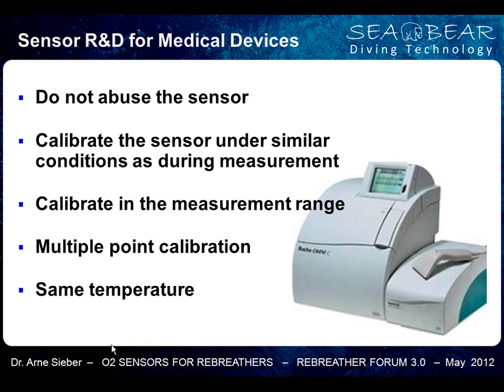The next point is, do a multiple point calibration. Define a span, and within this span I want to measure. I make a calibration point at the bottom, I make a calibration point at the top. This is the minimum I want to have, to see if I'm somewhere in the correct range. And then another very important thing: have the same sensor temperature during the calibration as during measurement.